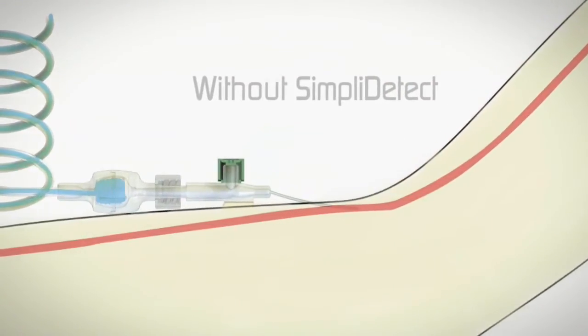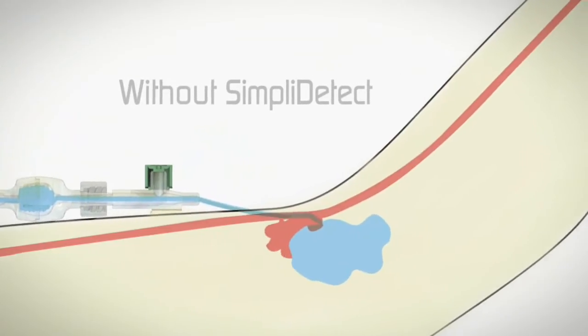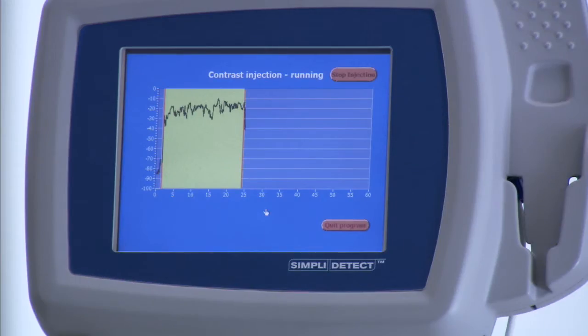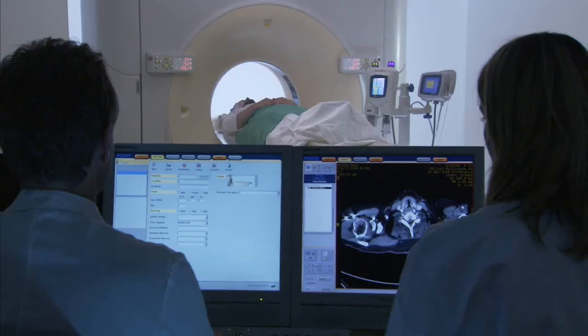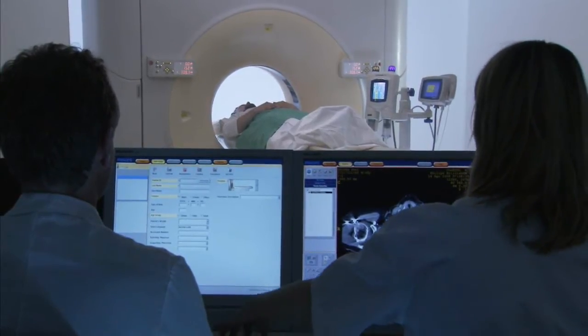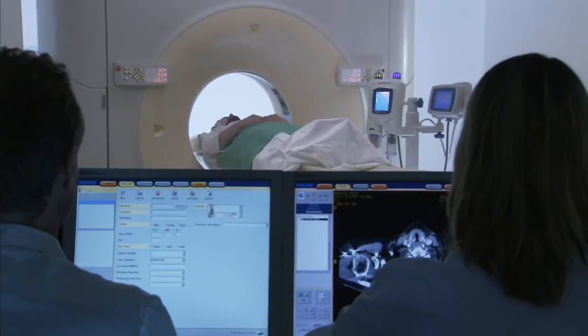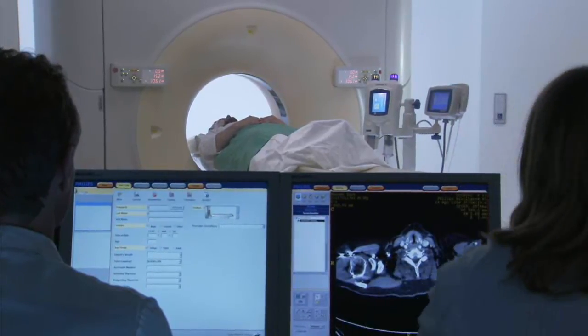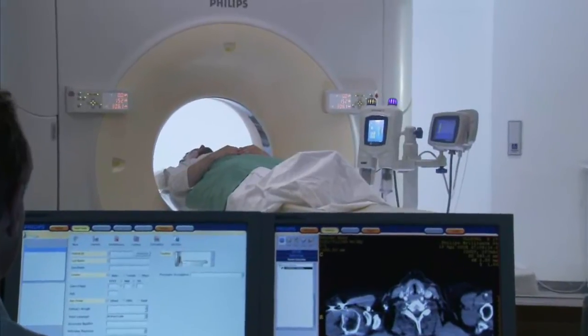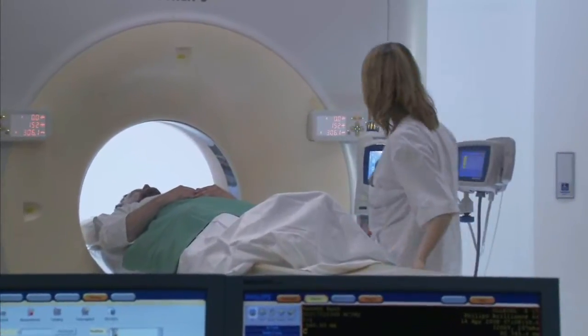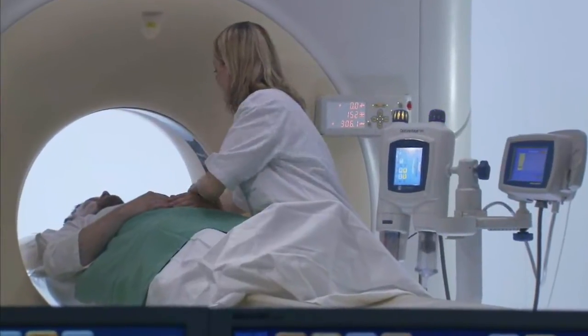Procedure-related complications are rare, but do happen and may be serious. SimpliDetect will continuously display information to the CT tech and allow focus on other important aspects of the injection. SimpliDetect has on several occasions shown no flow of contrast or saline in the patient's vein, contrary to our own belief. In our case, the cause has been kinked tubings or closed valves. At any given time, it will be possible to verify that the injection is going right, and should anything out of the ordinary happen, the CT techs will have the comfort of knowing that they will receive timely warning.